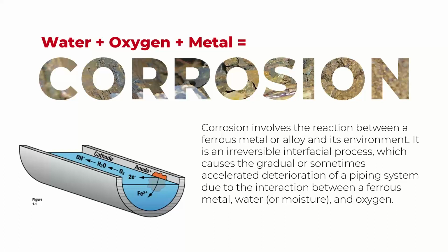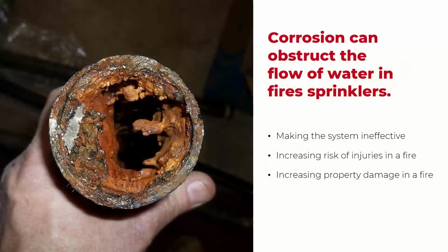And that's really what that oxygen-related corrosion is, what is having such an intense impact on all wet fire sprinkler systems. Corrosion is a problem in all systems, be it wet or dry, but in this case, I'm going to be focusing on wet system-related corrosion, and then I will be talking about some dry system issues towards the end.